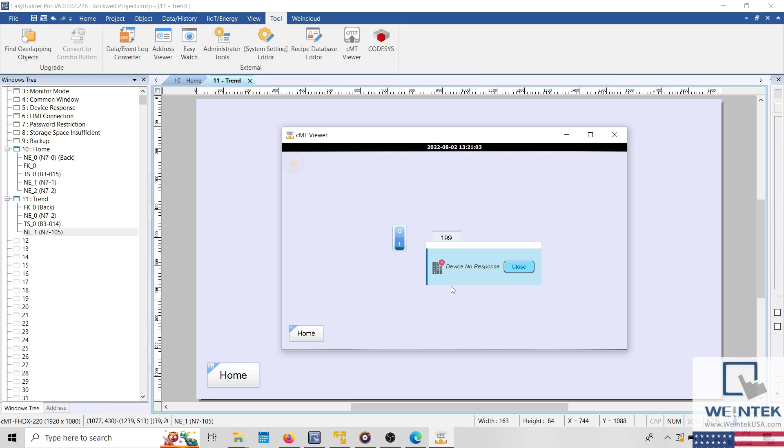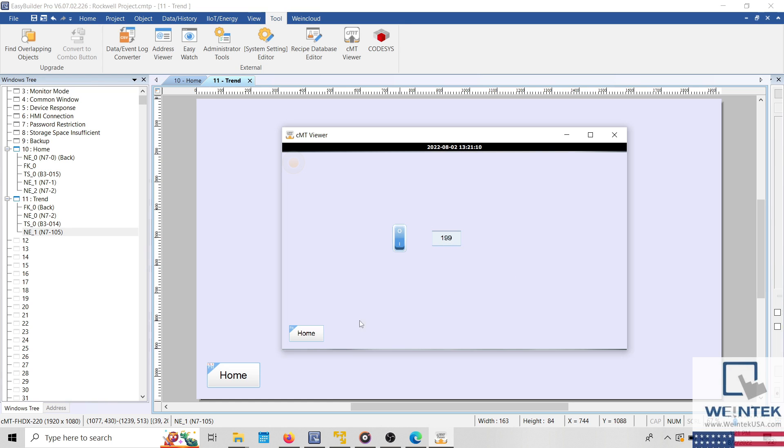If the device no response message is displayed on each window within your project, and certain objects that are addressed to the PLC continue to display accurate data, this indicates that there is some global object, like a macro, data transfer object, event alarm, or data sampling object that contains a tag or register that is not communicating with your device.